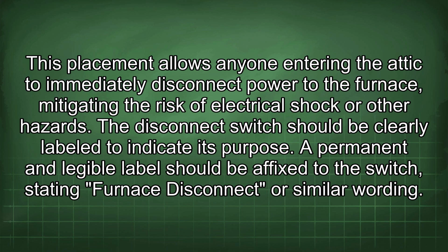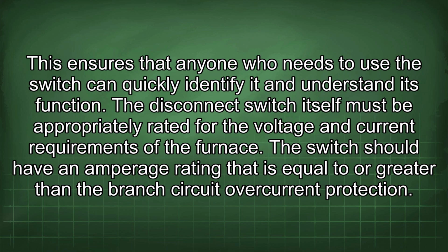This placement allows anyone entering the attic to immediately disconnect power to the furnace, mitigating the risk of electrical shock or other hazards. The disconnect switch should be clearly labeled to indicate its purpose. A permanent and legible label should be affixed to the switch, stating "furnace disconnect" or similar wording. This ensures that anyone who needs to use the switch can quickly identify it and understand its function.